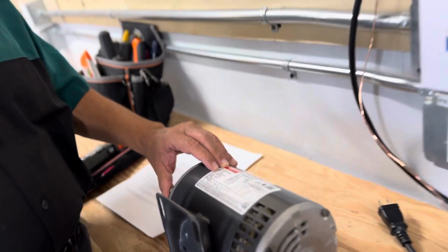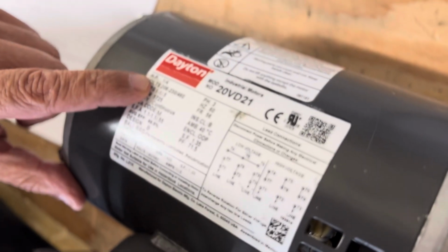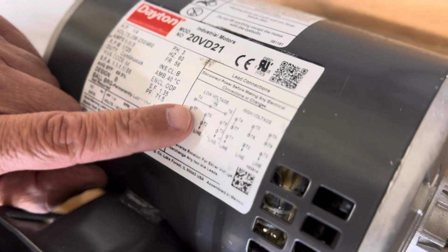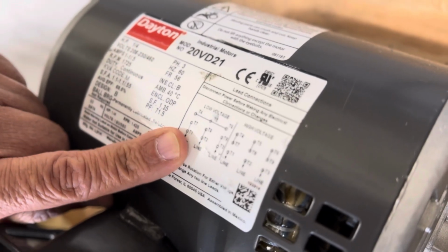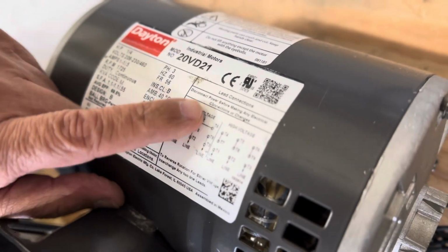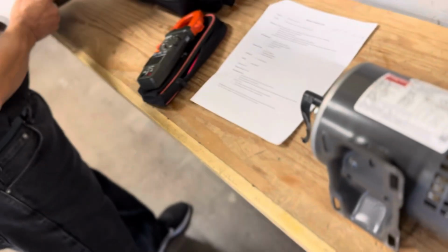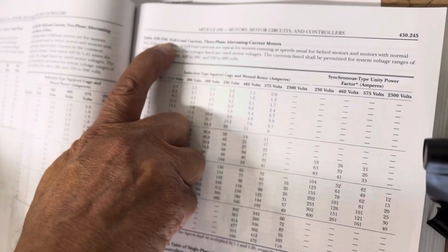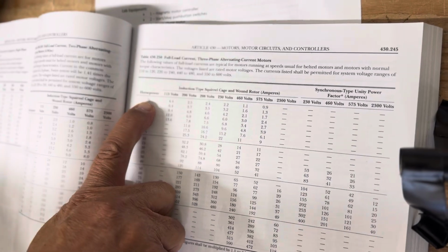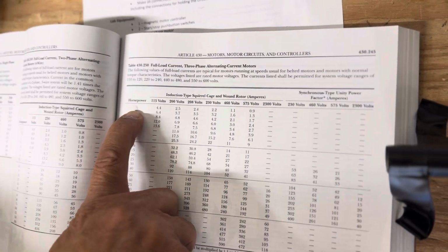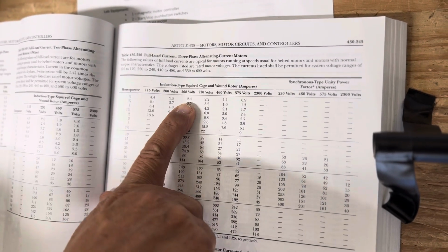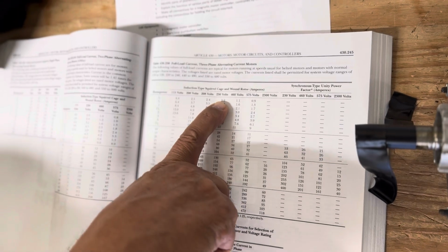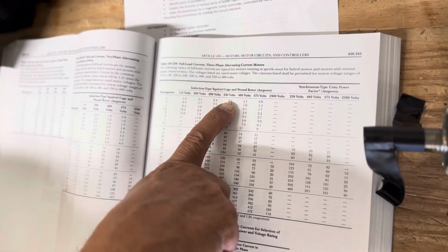Right here, we have this motor. It's a 1/4 horsepower, three-phase motor, and we are going to connect it to 220 volts, 208 to 220. This is for 480, so we are going to use this one. According to that, if I check the NEC table 430.250, we don't have 1/4 horsepower, so I will use half. For half horsepower, connected to 208 it is 2.4 amps, or at 220, 2.2 amps. That is the full load current that we are going to be consuming.